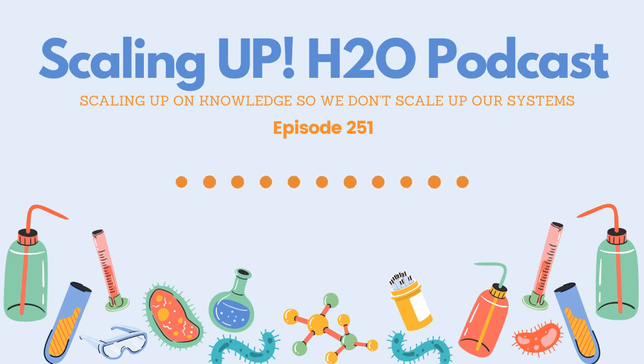I was speaking about a boiler. Let's say it's a cooling tower. Let's say everything is fine, everything's in calibration, but we're still seeing a low conductivity. So we walk out to the cooling tower. By the way, if you're not looking every single visit at the cooling tower, you're missing an opportunity for diagnostics. You go outside, you look at the cooling tower, and you see it's overflowing. Well, no wonder it's not concentrating up, it's overflowing. So now we have to figure out why that is going on.